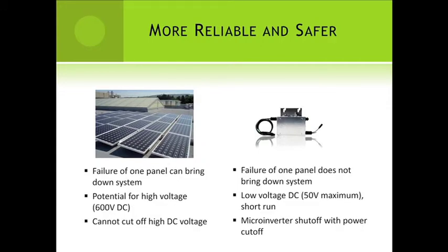More reliable and safer: the failure of one panel does not bring down the system. One of the nice features of a microinverter is a shut-off power safety mechanism. If it doesn't sense that your main distribution panel is sending current to your building, your microinverters will immediately shut down. So you just need to turn the breaker on and off, and the microinverters will turn off as well.